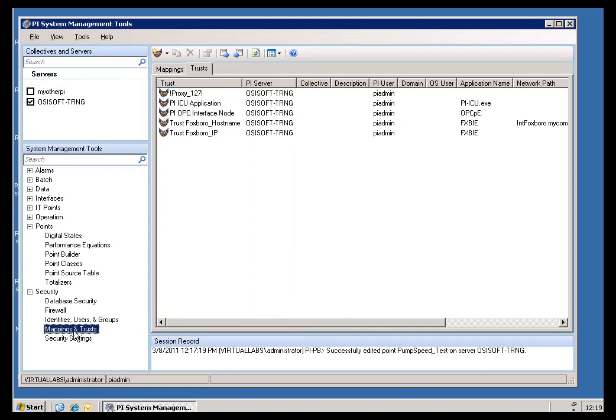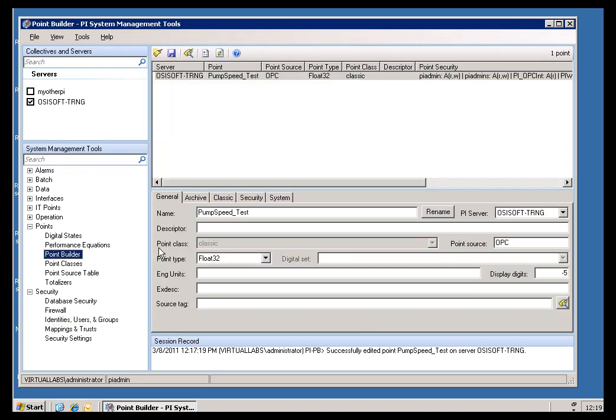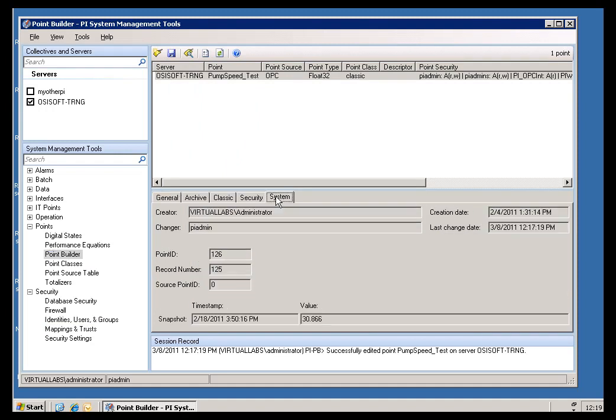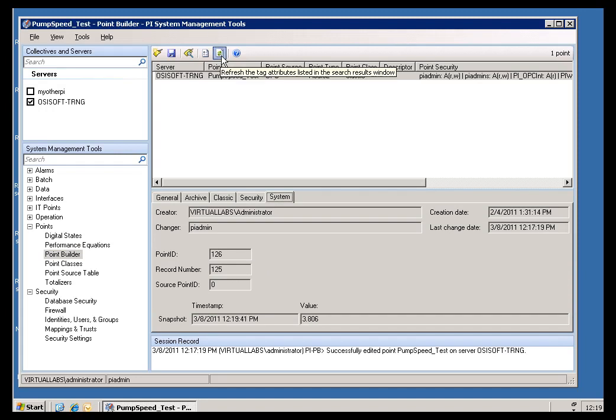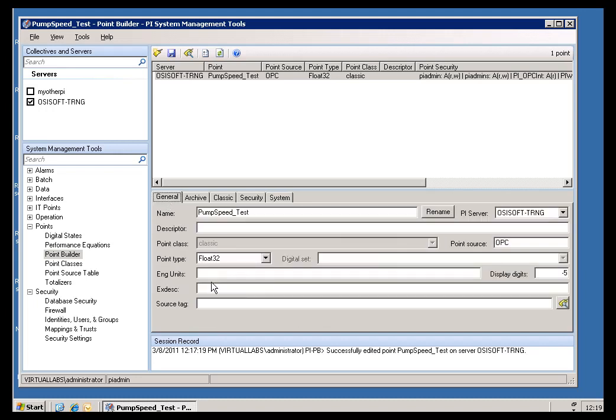I just waited two minutes, so the Interface should have gone out and scanned for that update to that Tag. Let's go take a look at the Tag, see if it's got a value that's been updated. I don't see anything here. This is not updated. I'll go ahead and refresh this. Yeah, there we go. I've just refreshed that. It seems to be updating and having good data. I'm guessing, by eliminating this mistake here, the Interface has picked up the change, and it's gone ahead and started sending data again.